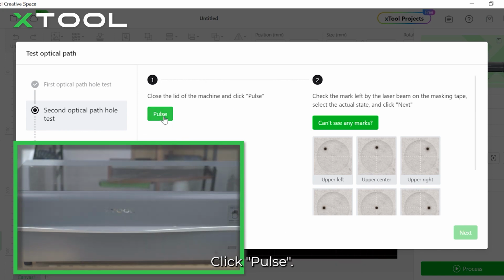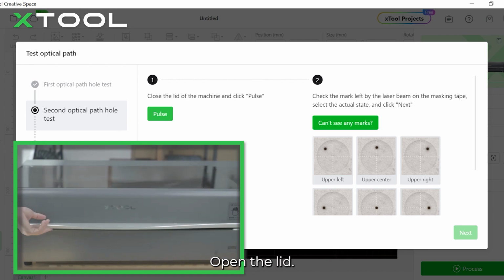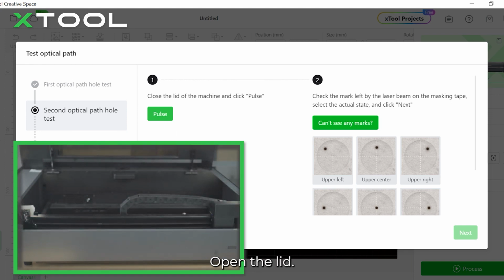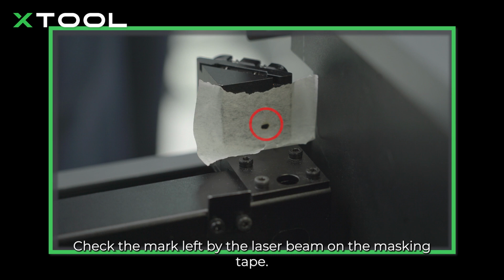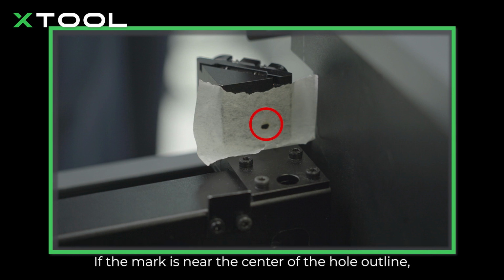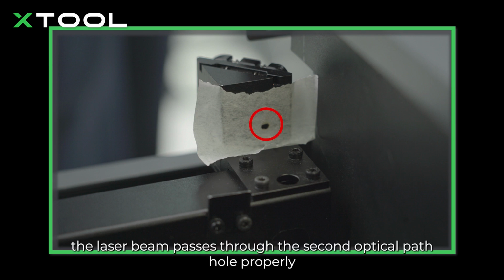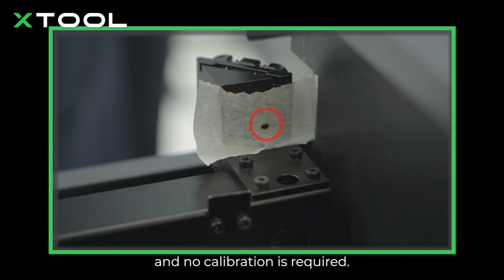Click Pulse. Open the lid. Check the mark left by the laser beam on the masking tape. If the mark is near the center of the hole outline, the laser beam passes through the second optical path hole properly, and no calibration is required.